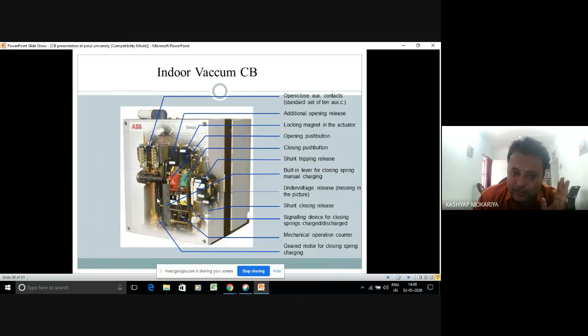After that, the subsequent commissioning tests are noted. After those commissioning tests, the reports are sent to the authority of the functioning. During this commissioning test, if something goes wrong, the manufacturer is immediately informed: sir, we find this type of thing in a breaker, please correct it. And this is mostly done for every type of equipment.